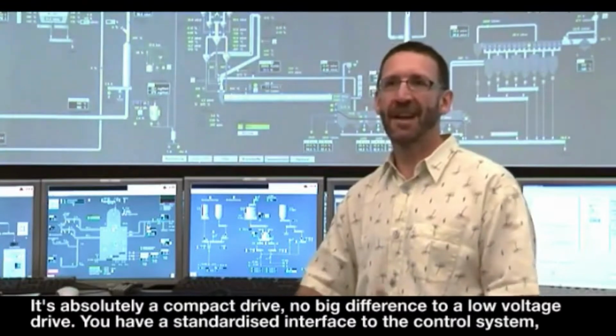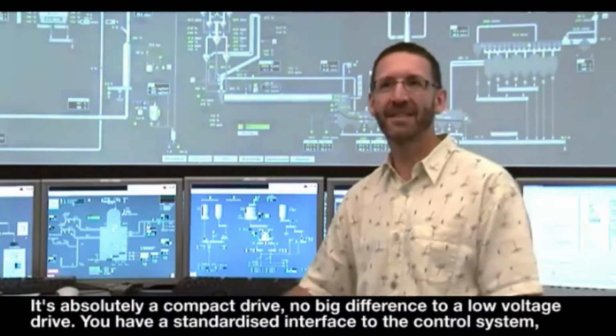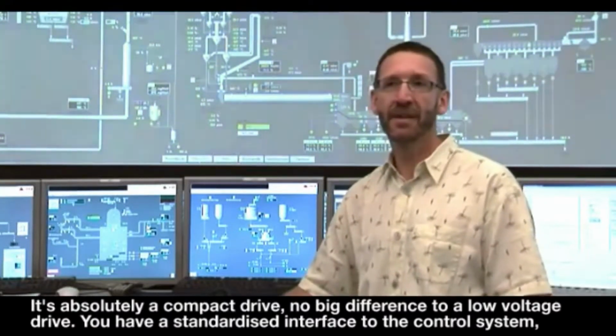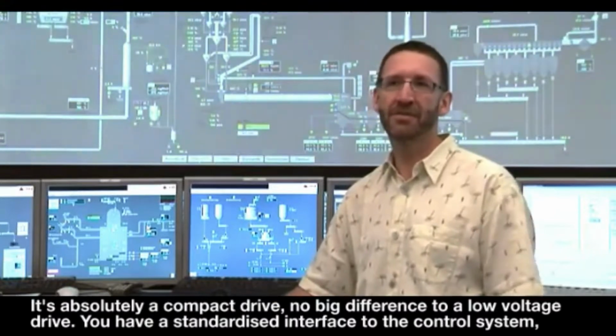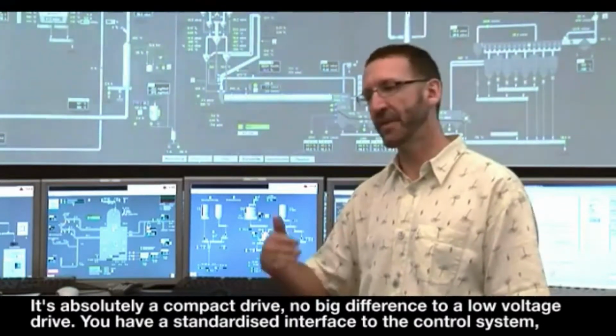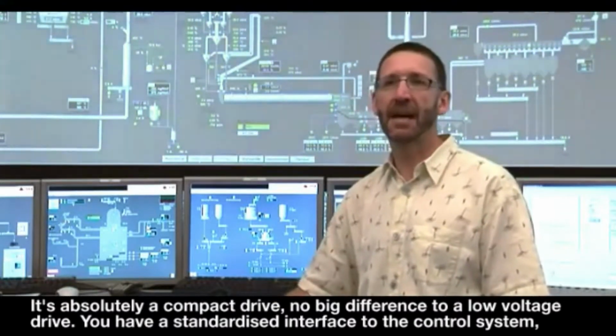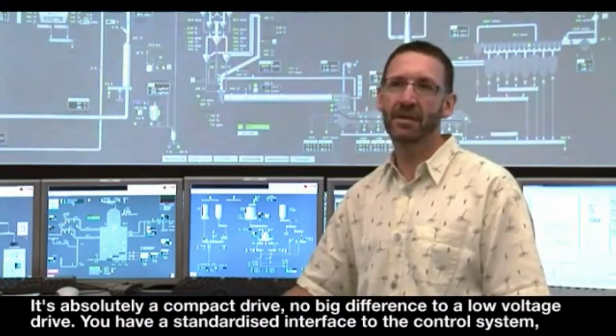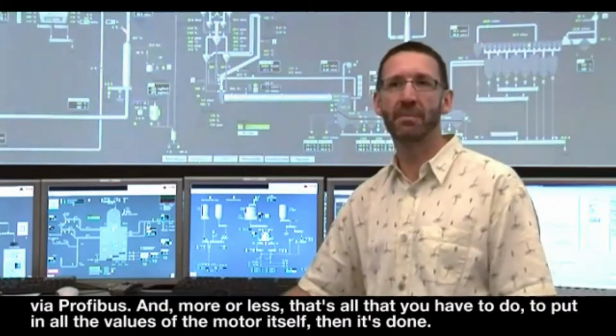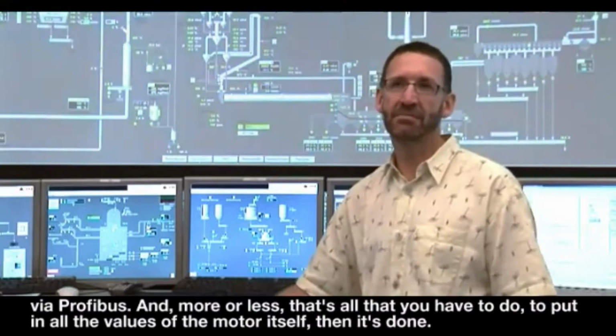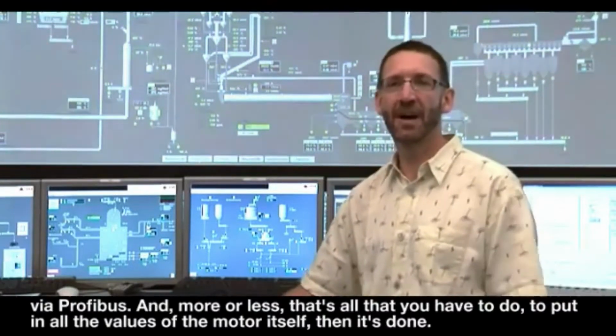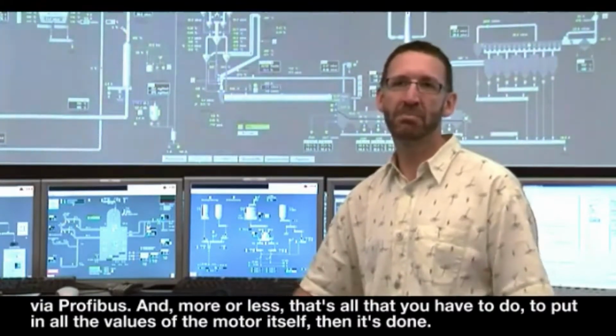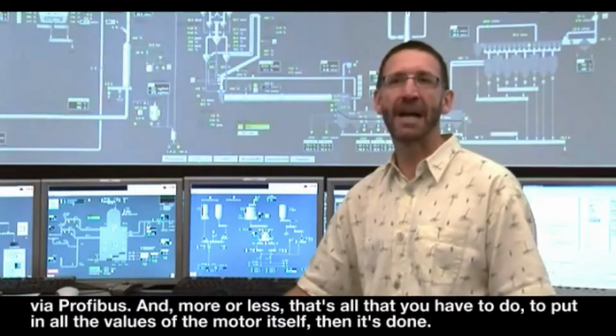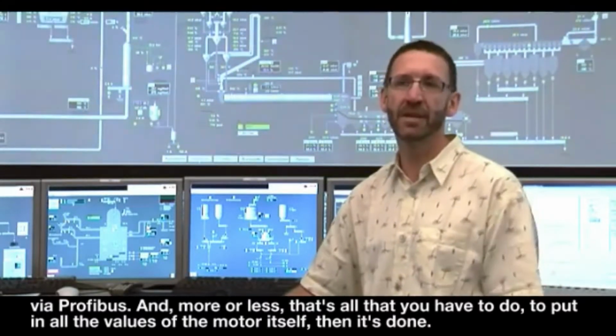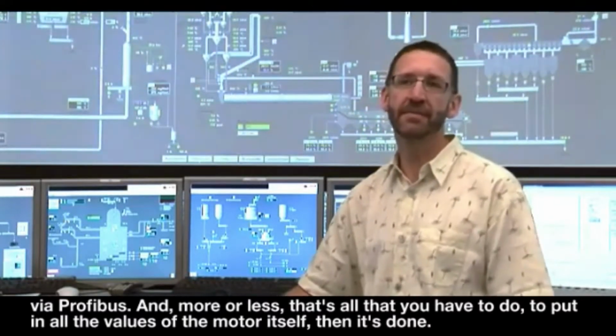It's absolutely a compact drive, no big difference to a low voltage drive. You have a standardized interface to the control system by Profibus, and more or less that's all that you have to do to put in all the values of the motor itself, and then it's done.